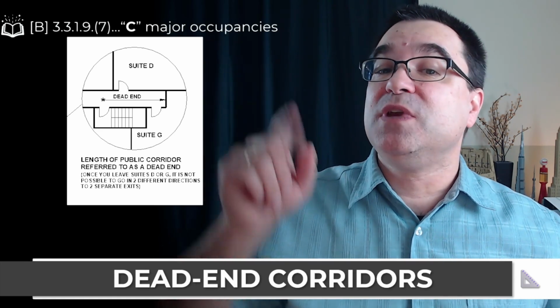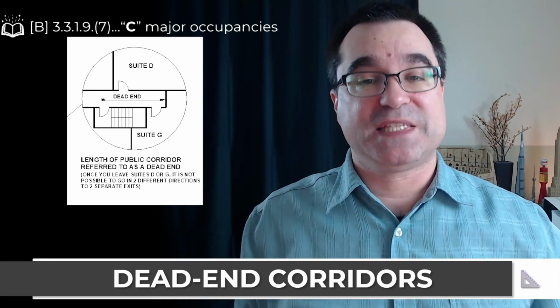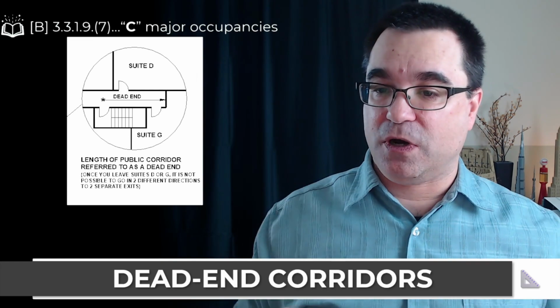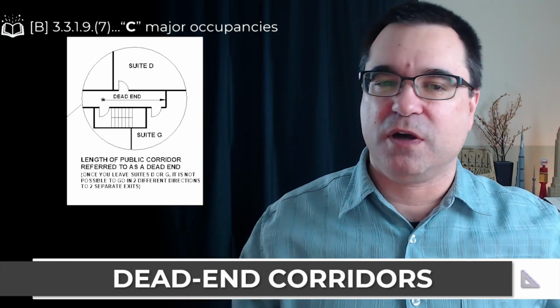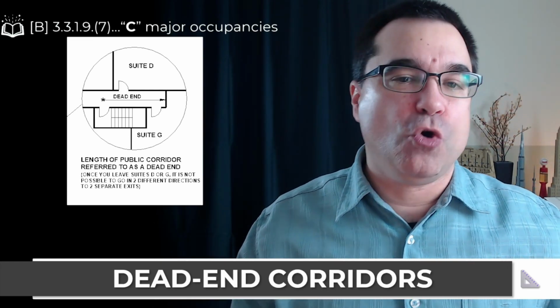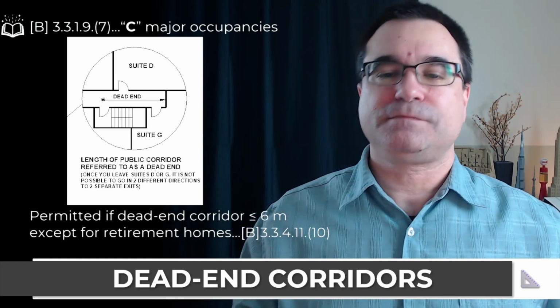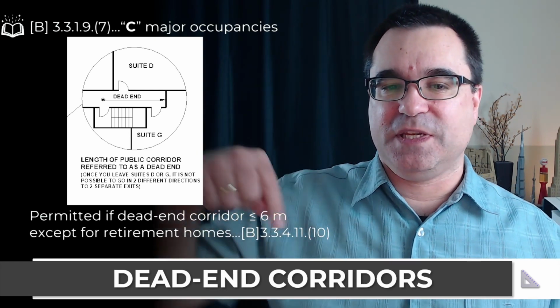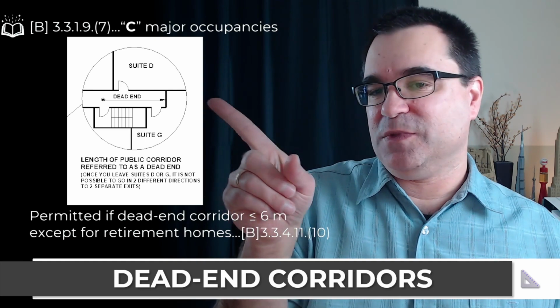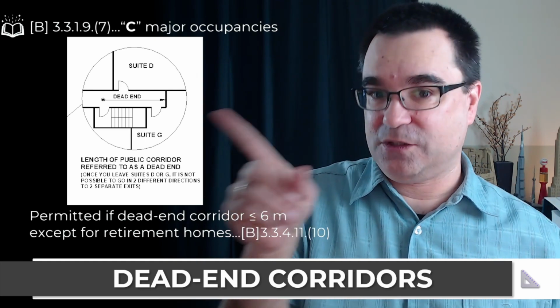Under sentence 3.3.1.9.(7) for C major occupancies, so residential occupancies, dead-end corridors are allowed only if they're less than 6 meters, right? And the distance is from the middle of the doorway to an exit to that dead end.